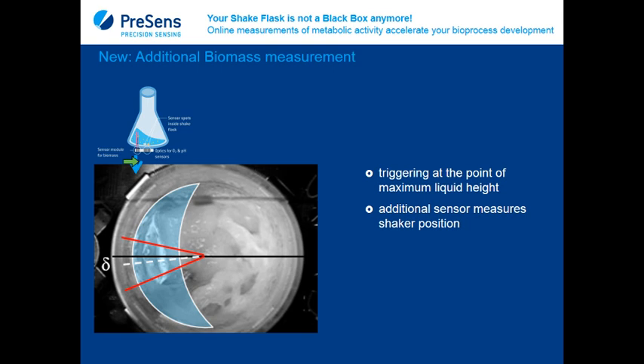Actually, we have both. We have our multi-use glass flask with integrated oxygen sensors. They need to be calibrated by the user. And we also have calibration-free disposable sensors with integrated oxygen and pH measurement. The biomass measurement is possible in both systems, in glass or plastic systems.